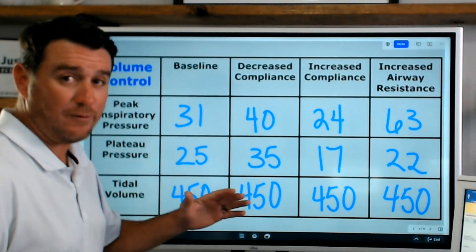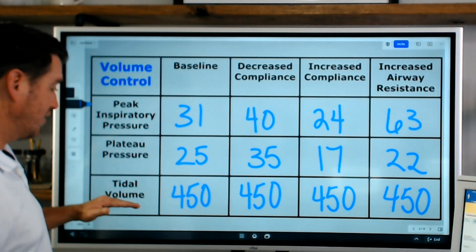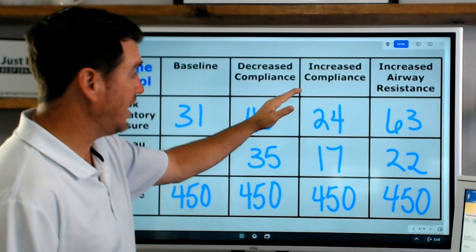I've been taking notes on all the parameters we gathered and now it's time to analyze them. We were in volume control and we compared baseline versus decreased compliance, increased compliance, and increased airway resistance — looking at peak inspiratory pressure, plateau pressure, and tidal volume. Everything we know about volume control is confirmed right here: no matter what happened with compliance or resistance, tidal volume remained constant. Volume control means constant delivery of a set tidal volume, and pressure varies based on compliance and resistance.